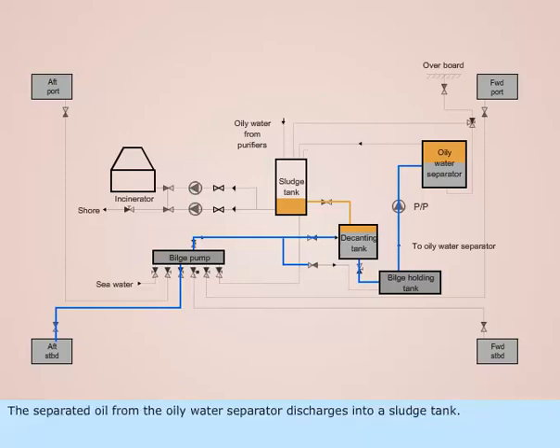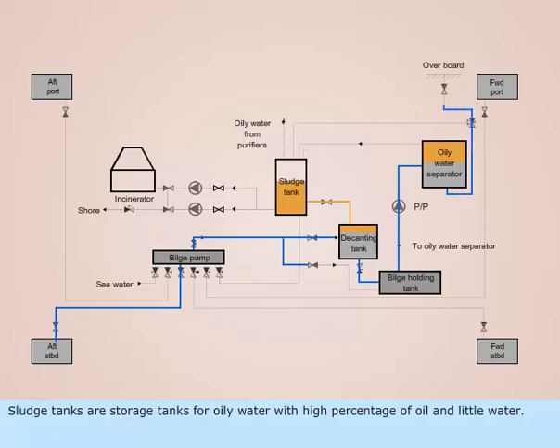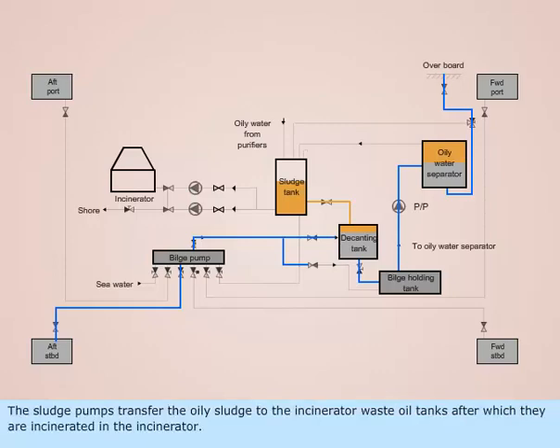The separated oil from the oily water separator discharges into a sludge tank. Sludge tanks are storage tanks for oily water with high percentage of oil and little water. The sludge pumps transfer the oily sludge to the incinerator waste oil tanks, after which they are incinerated in the incinerator.